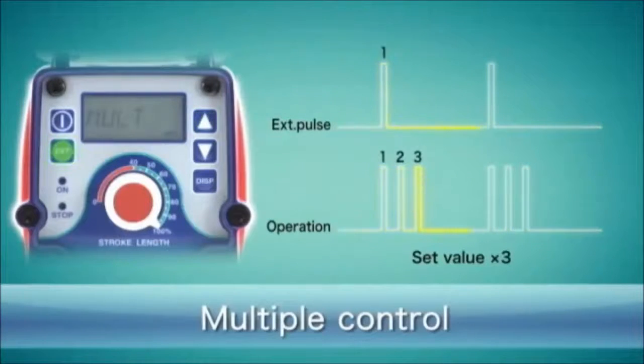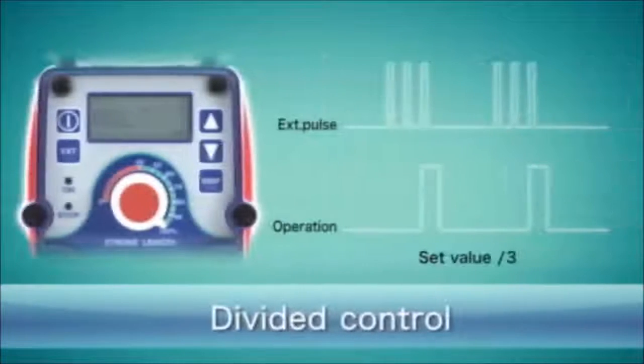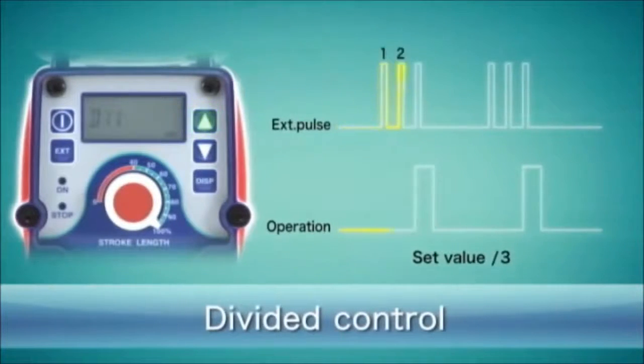The multiply control can be used to set multiple pump strokes for every digital input. The divide control allows the pump to stroke for a predefined number of input signals.